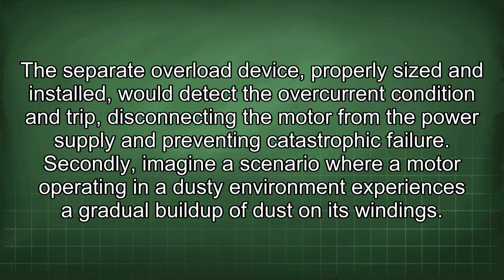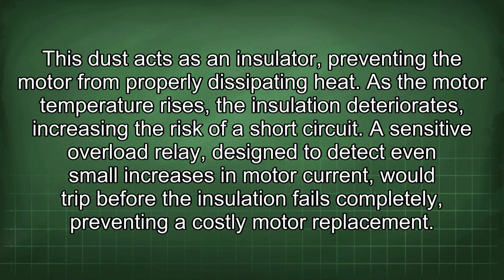Secondly, imagine a scenario where a motor operating in a dusty environment experiences a gradual buildup of dust on its windings. This dust acts as an insulator, preventing the motor from properly dissipating heat. As the motor temperature rises, the insulation deteriorates, increasing the risk of a short circuit. A sensitive overload relay, designed to detect even small increases in motor current, would trip before the insulation fails completely, preventing a costly motor replacement.